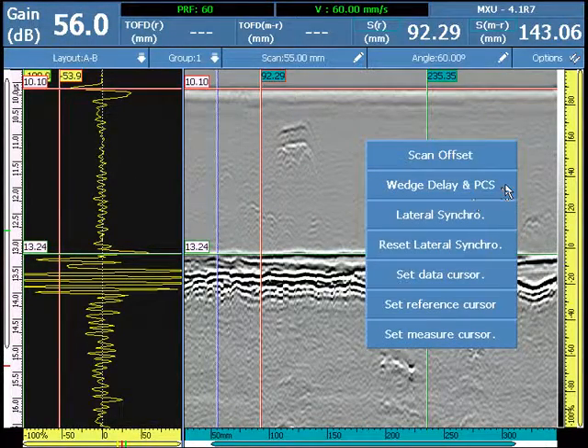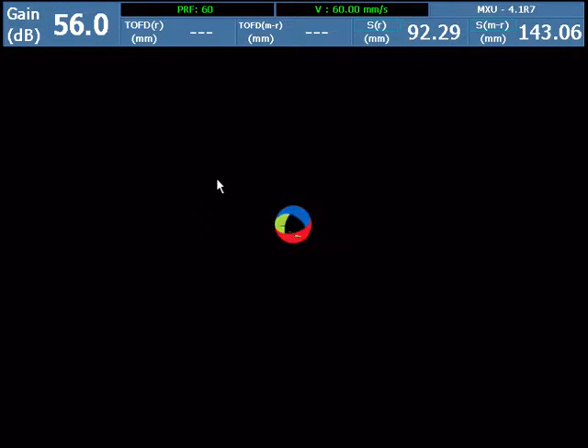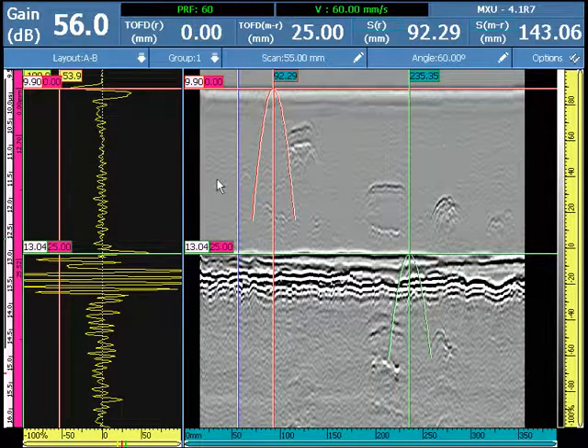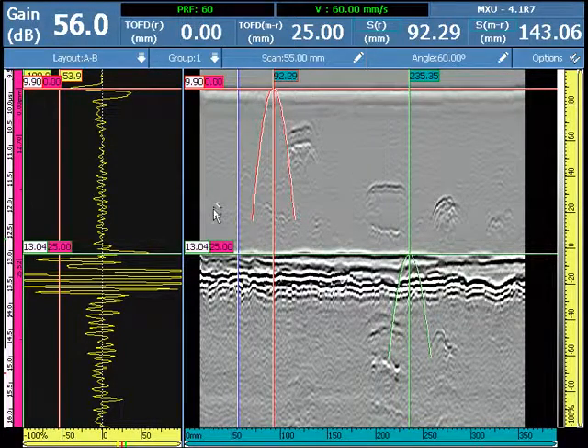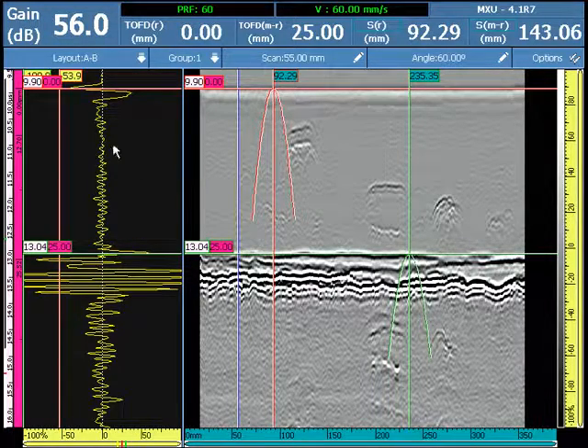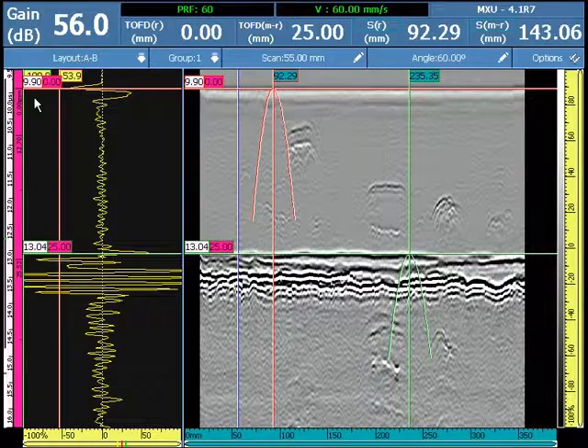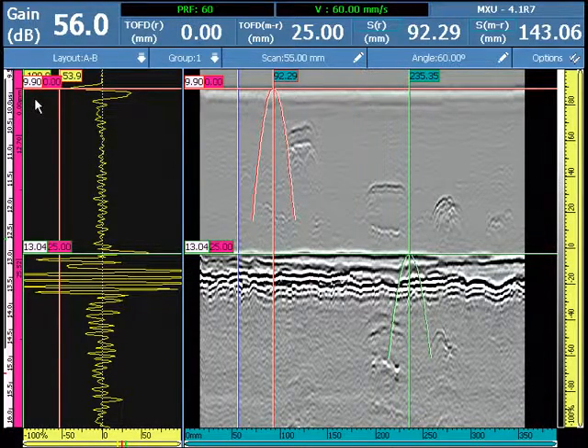Select Wedge Delay and PCS. An algorithm is performed. This correction in the UT-axis is called Linearization. We can see that now for the values in the cursors, we have microseconds and millimeters.